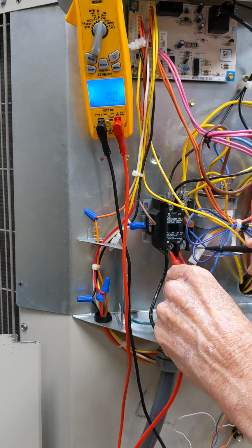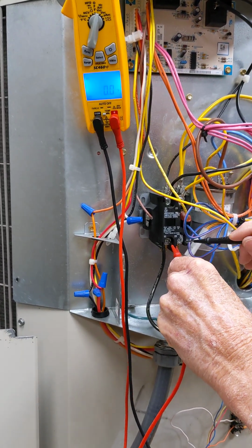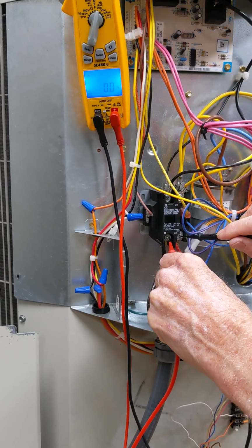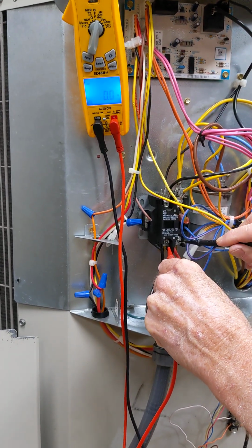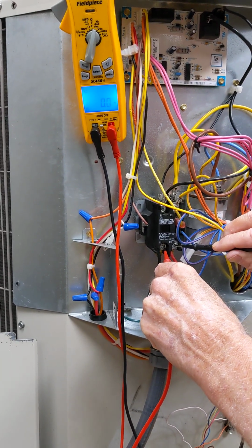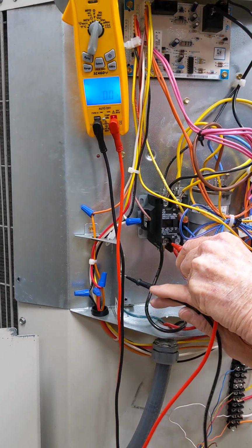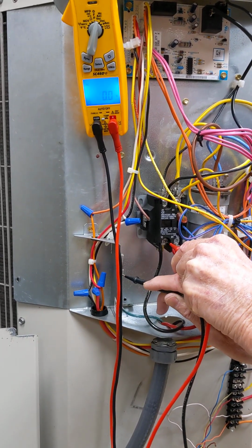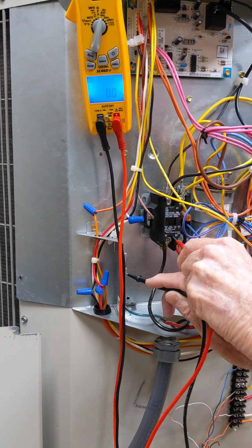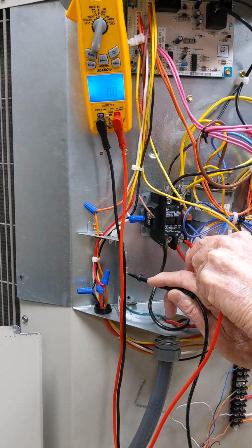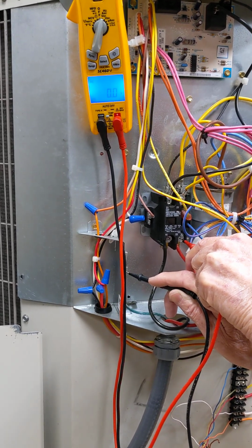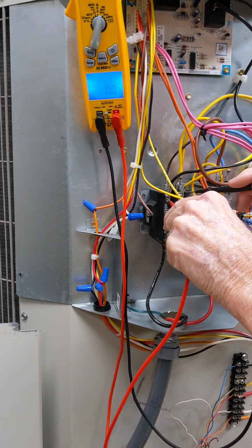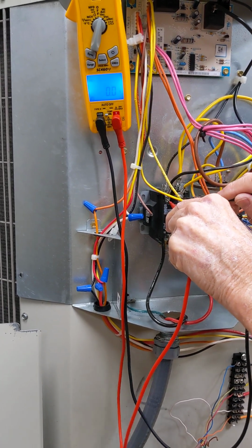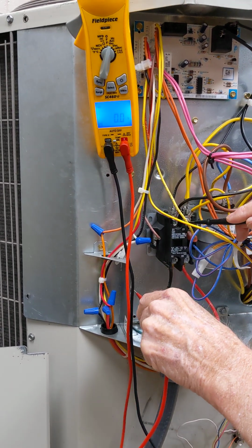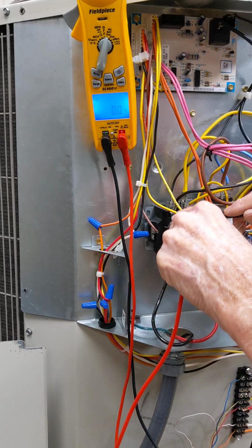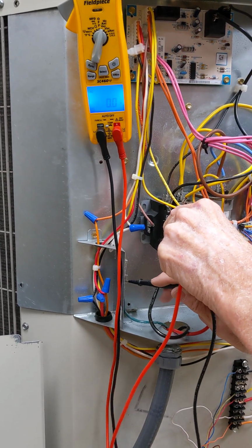Okay, I want to check the bottom where the wires come in for high voltage to run the motors. I got nothing. Just to be extra cautious, I'm going to take one leg and go right to the ground screw. I got nothing. I'm going to stay on the ground screw and go to the other side. I got nothing. Okay, I'm going to go to the top. I should have nothing, and I got nothing. And to make double sure, I'll just go back to the ground screw on each side. I got nothing. Okay.